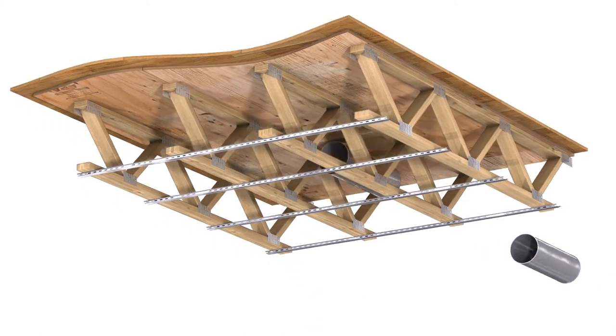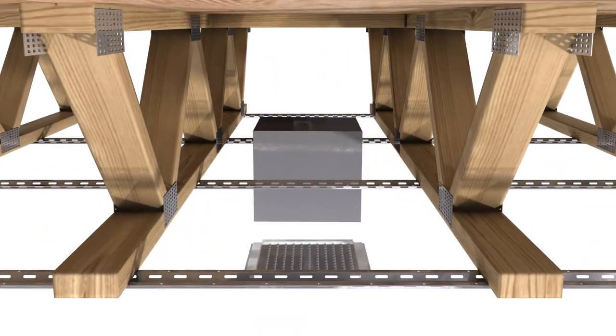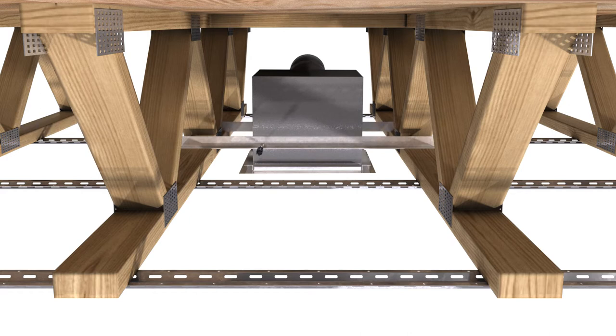Greenheck also offers two different mounting options to make installations quick and easy. The first is the hanger method, which allows the damper to be supported from above using steel straps, wires, or angles. The second mounting option is the base mount method, which utilizes two mounting angles to support the damper at the bottom chord of the truss.